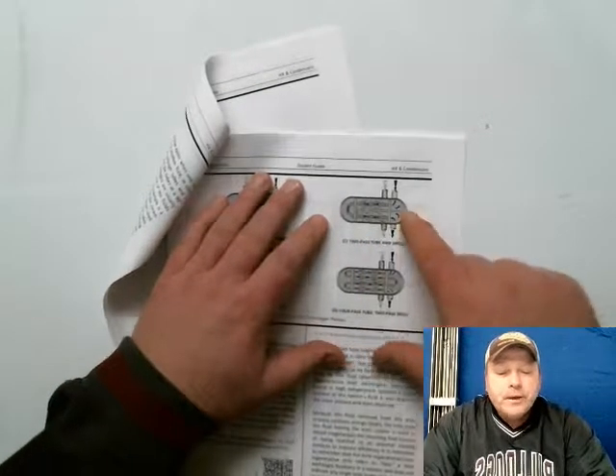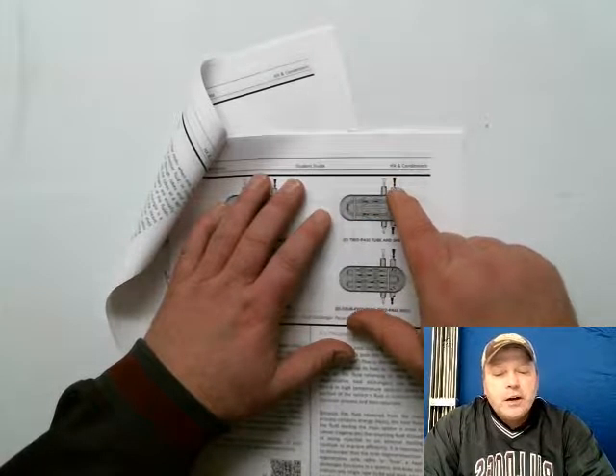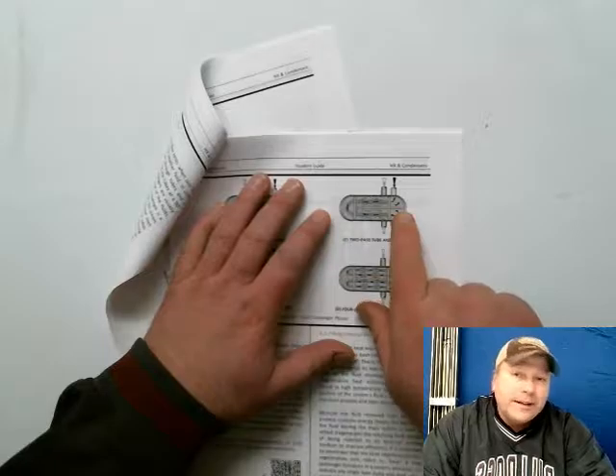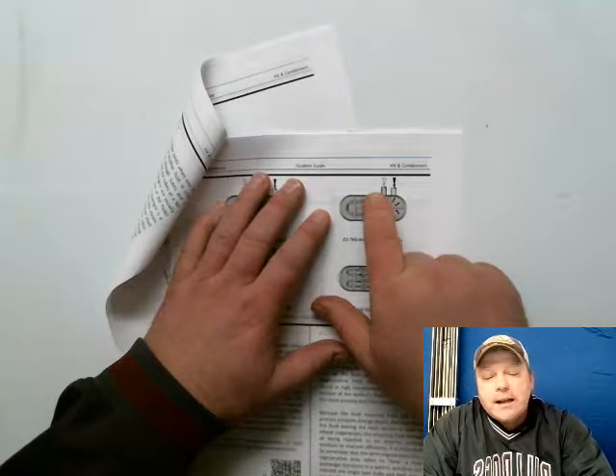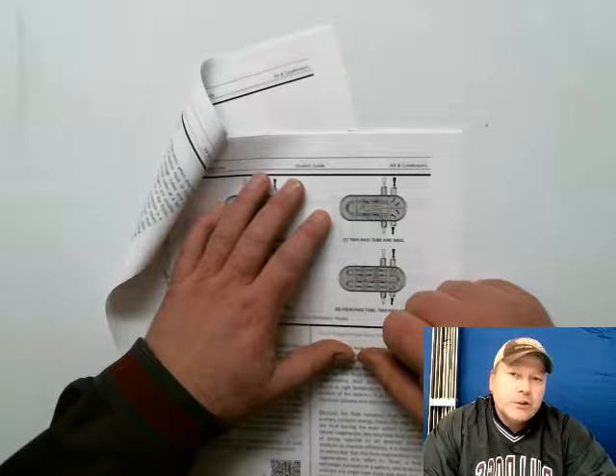Then you come up here, and you have what's known as a two-pass, two-pass. The shell is forced to go one length, and there's a divider there, and then it has to go the length of the tubes again, just like the tubes themselves did. So this is a two-pass tube and shell heat exchanger.